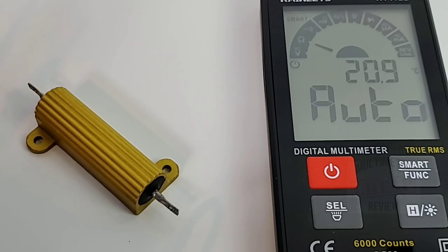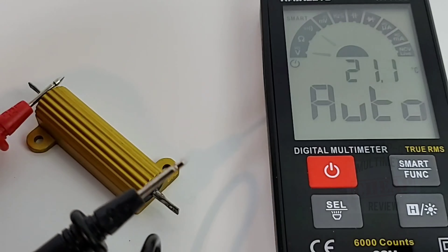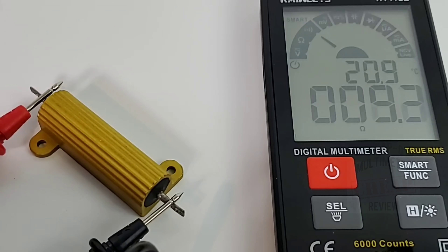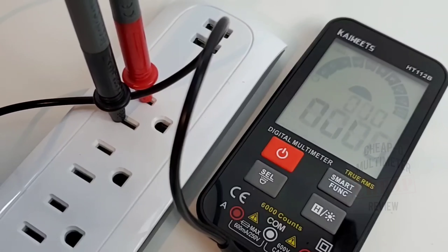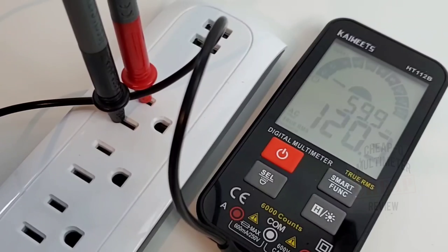Now in low resistance mode — still in auto mode — we'll check low resistance. This will probably engage the continuity since it's under 50 ohm. 8.25 ohm is what we want to see. Reading 8.3 — looking good. Let's check AC voltage in auto mode — nice and fast, looking good, and there is the frequency at the top: 60 hertz. Beauty.